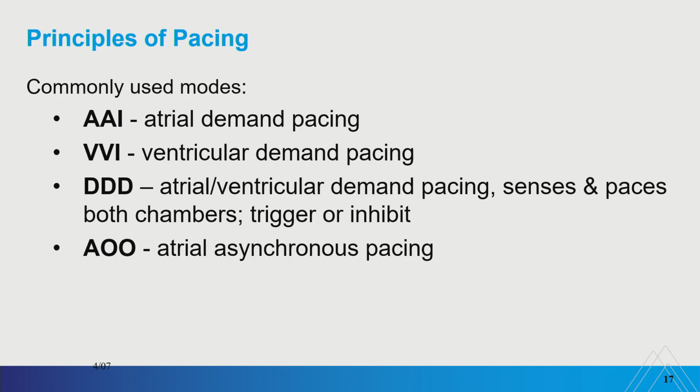So you see how this pacemaker on DDD mode can A pace at the low rate, AV pace at the low rate, or ventricularly pace at any rate between the low rate and the high rate that's set on the pacemaker. Some pacemakers, depending on the brand or how they're set up, have a high rate set at 110. Some of them will be set up to always be 30 higher than the low rate. I prefer it to be 110 because I might want my pacemaker set at 50, but I might want to pace ventricularly if my P waves are going across the screen at 90. I don't want to be limited to that.